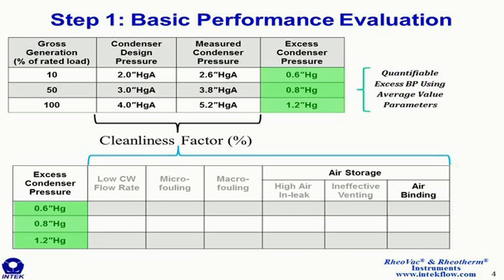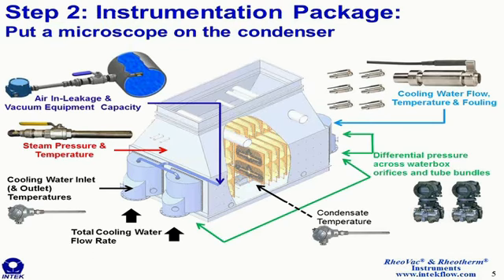So the recommended approach for the second step, step 2 of the engineering study, is to perform a more detailed condenser test to quantify the magnitude of performance loss from each of these 6 mechanisms. And instrumentation is needed to perform this advanced evaluation. This slide shows instruments used for the advanced evaluations. ASME PTC 12.2 is used as a guideline for selecting instruments.